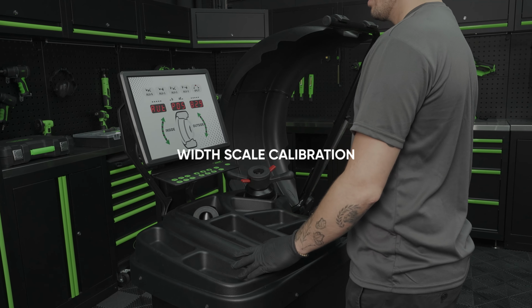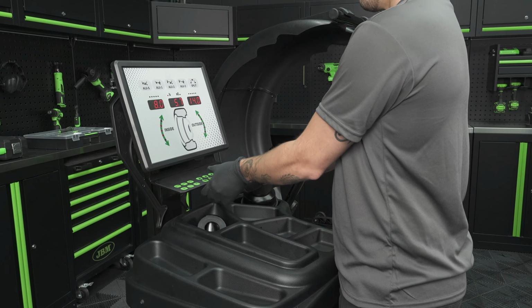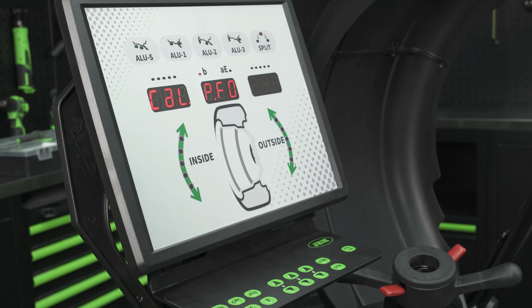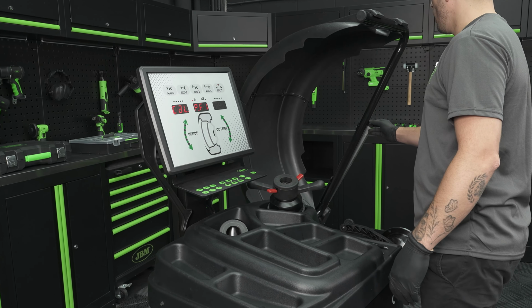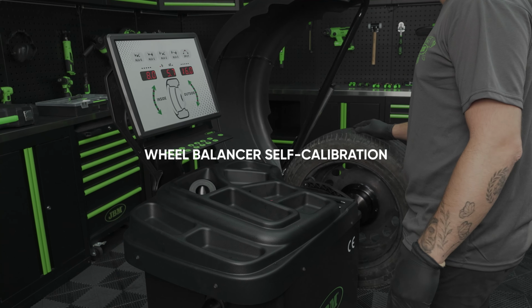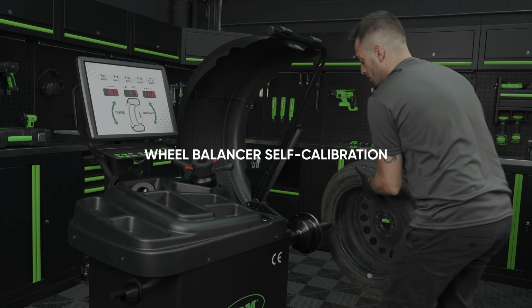To access this procedure, press and hold the stop key and press the B+ or B- key. With the width measuring gauge in its initial position, press the ALU key. Then, move the width measuring gauge and place the head against the shaft mounting plate. Press the ALU key again to confirm. Finally, we will see the self-calibration procedure.